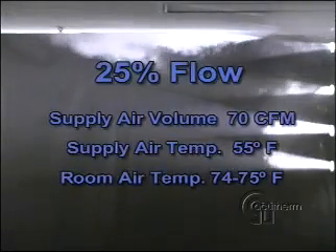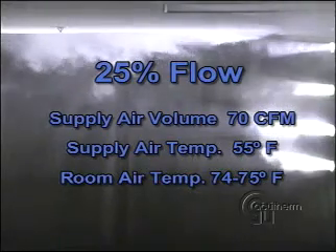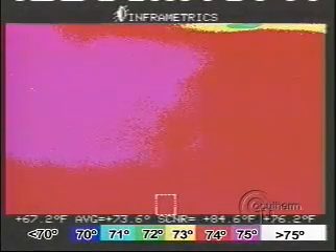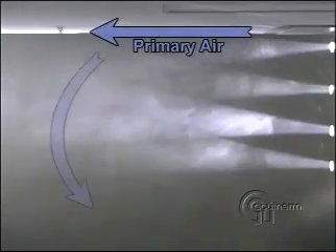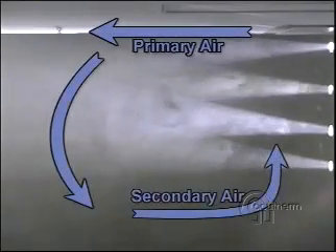We are now looking at the same Thermafuser module turned down to 25% flow or approximately 70 CFM. While the throw is somewhat reduced, Coanda is maintained because the exit velocity remains close to 1,500 feet per minute. Looking at the thermal image of the 70 CFM flow, we can see that the colder primary air — black, blue, green, and yellow — remains at the ceiling and that room temperature is at a constant 74 to 75 degrees Fahrenheit, red and magenta. The Thermafuser's high discharge velocity provides good mixing even at this reduced flow, with high velocity primary air providing good entrainment of secondary air and thorough mixing.